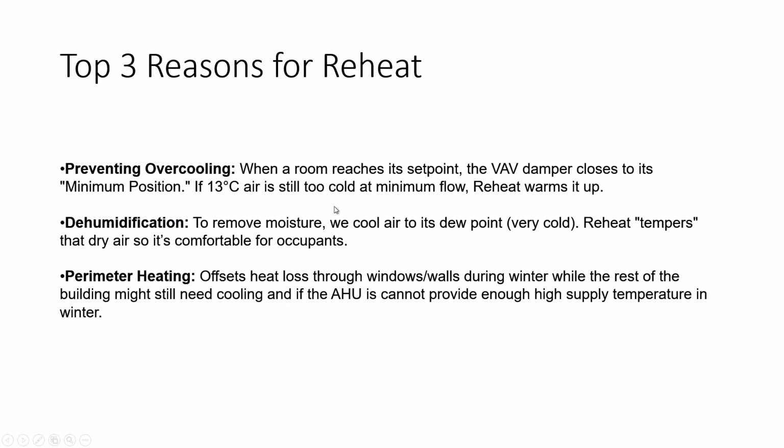For example, there is no requirement of cooling in the room and the VAV is closed, but there is a certain minimum airflow going to the space. At that stage, 13 centigrade is too cold for the room, so reheat warms it up to maintain a certain temperature.